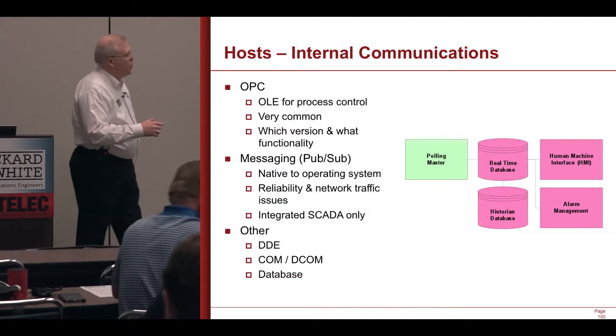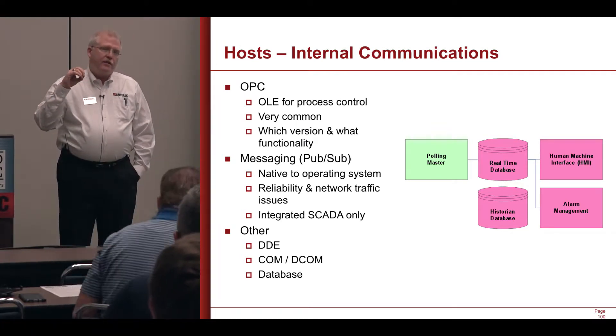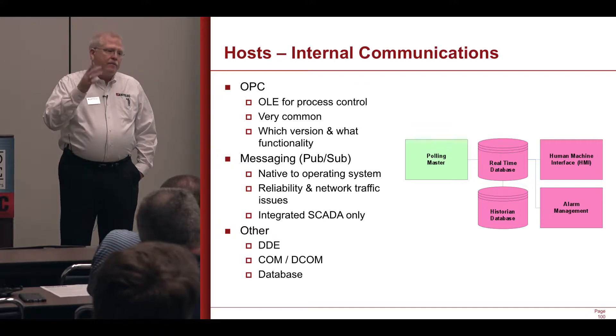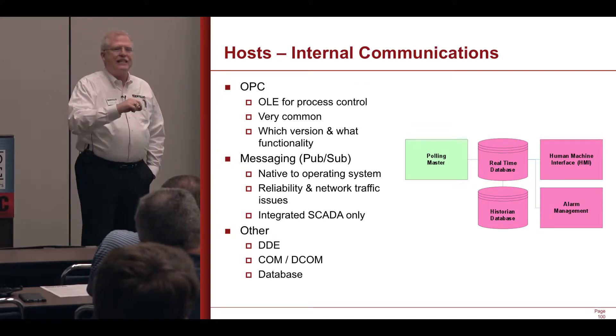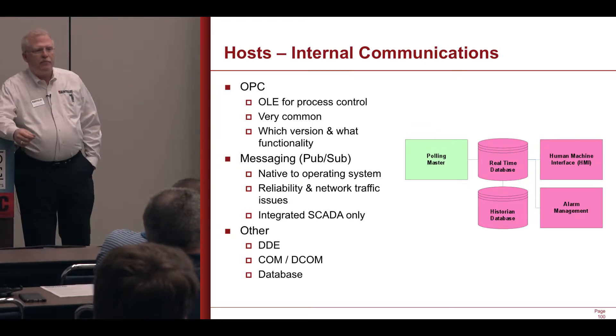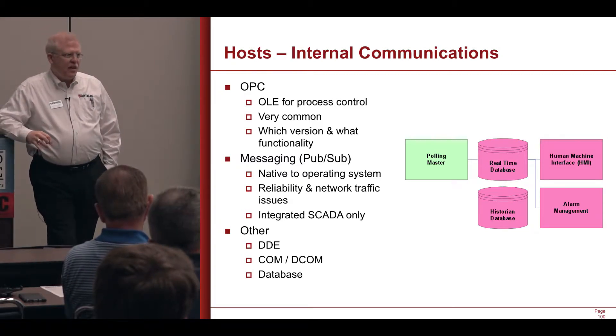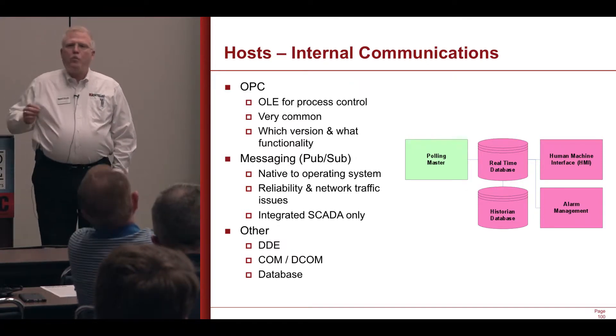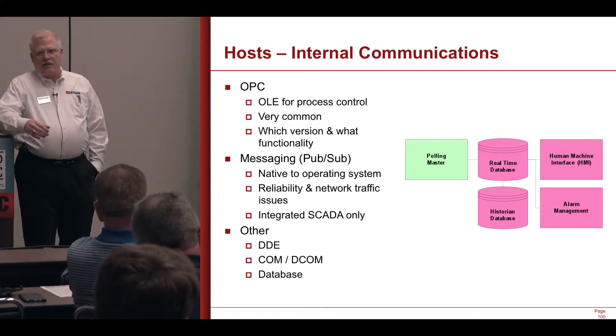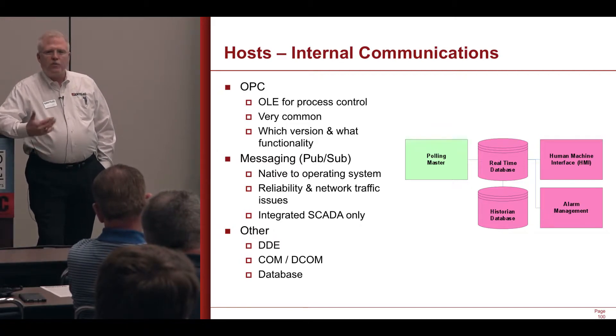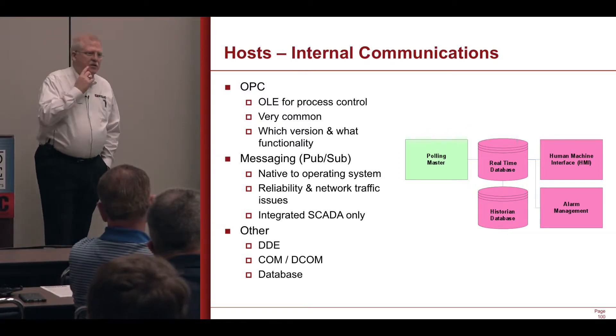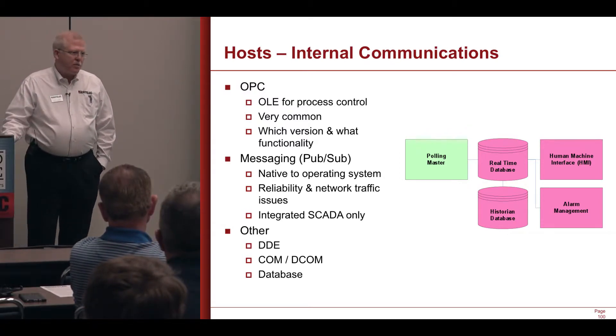A comment about OPC: OPC is OLE for process control. It is the primary mechanism for moving real-time data between devices and software applications. There are two kinds of OPC. OPC DA — OPC Data Access — is based on Windows COM/DCOM, so it only runs on Windows and requires creative COM configuration. It works great within a machine, okay across a local area network, and not at all across a wide area network. OPC UA — Universal Access — is the new standard; it has encryption, built-in tunneling, and security control down to the tag level. Most software products say they support OPC, but many only support DA and not UA.